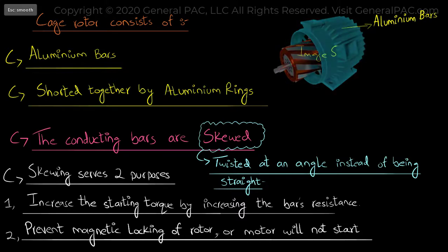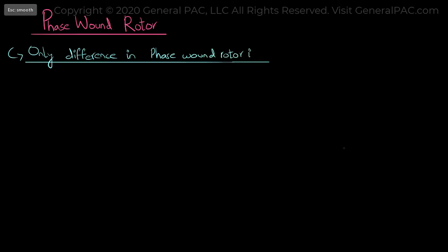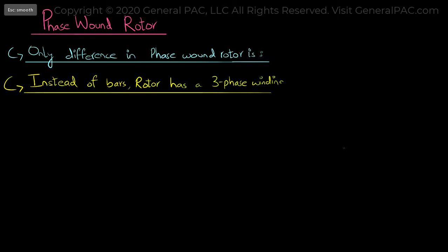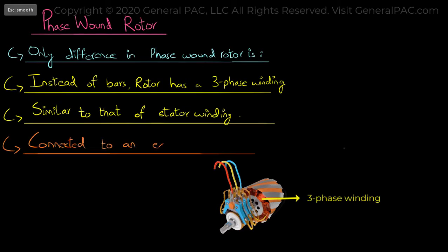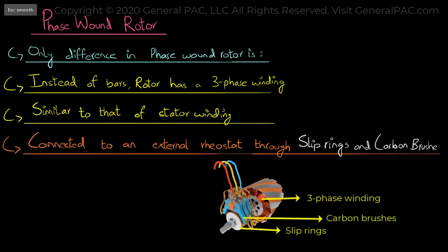So let's move on to the discussion of phase wound rotors. The only difference in phase wound rotors is that instead of having bars, the rotor has three phase winding which is similar to that of a stator winding. The windings are connected to an external rheostat through slip rings and carbon brushes which are present on the rotor shaft.